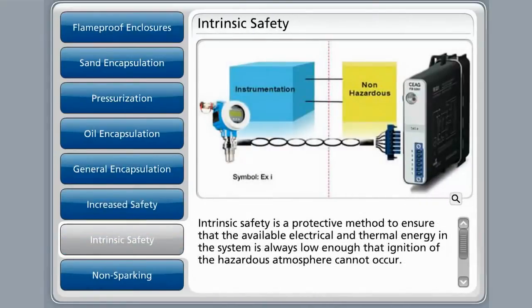Intrinsic safety is a protective method to ensure that the available electrical and thermal energy in the system is always low enough that ignition of the hazardous atmosphere cannot occur. This is achieved by ensuring only low voltages and currents enter the hazardous area, and all electrical supply and signal wires are protected by safety barriers. The general application would be used for measuring and control engineering, data engineering, and low electrical valves.